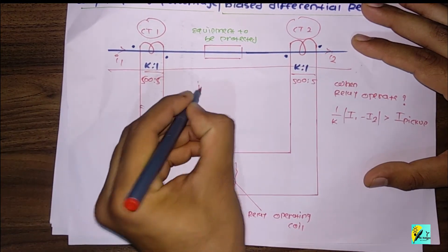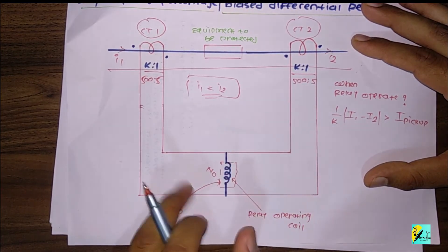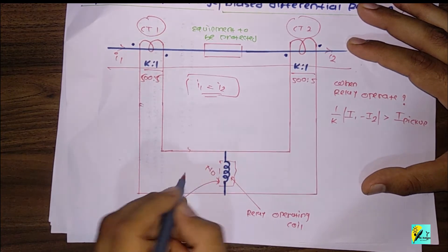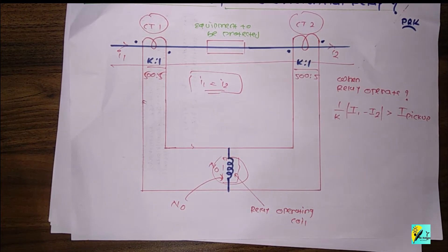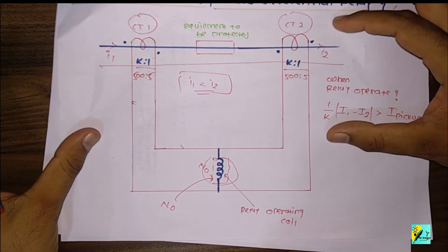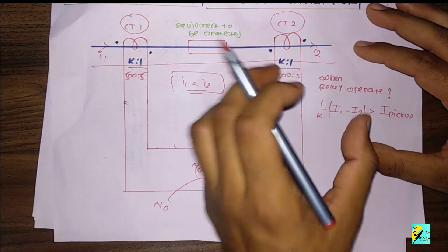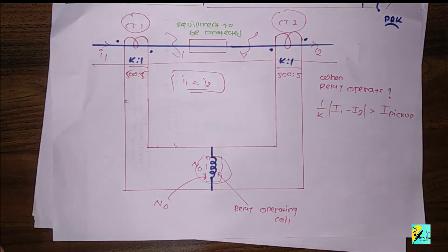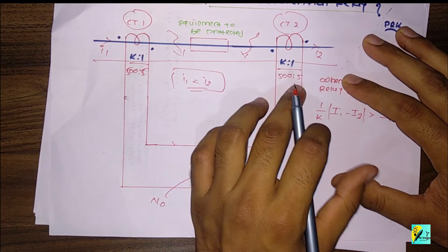In normal case, I1 should be equal to I2 — incoming current equals outgoing current. In that case, no extra current will circulate in the secondary and the relay operating coil will not operate. But there is a condition: even if there is no fault in this particular section, the relay may still get operated if the transformation ratios are different.